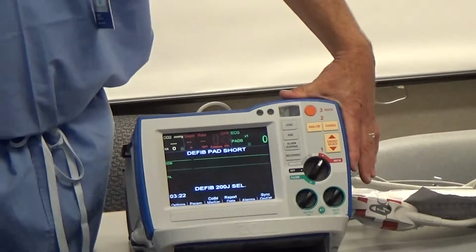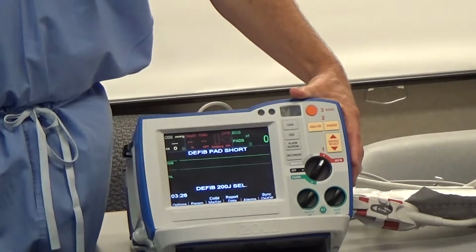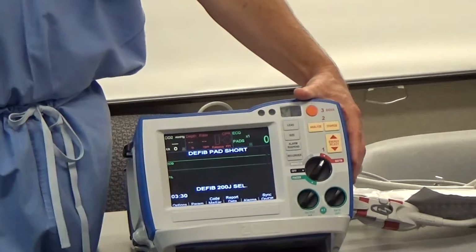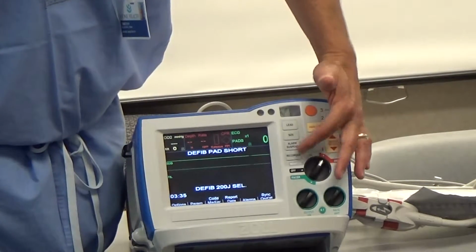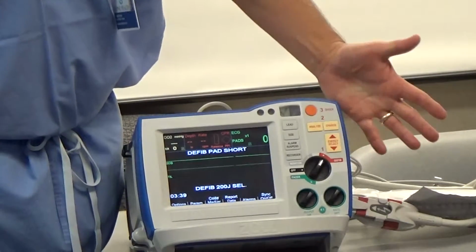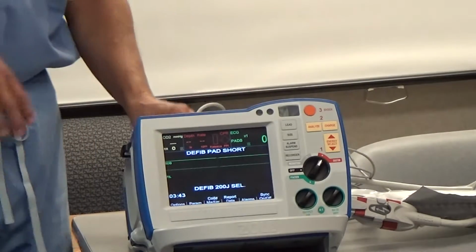Well, let me do a couple of things here. Here's your lead. It's always a good thing to change your lead if you want to. If you're not getting what you want to see, you can push that button and change it to another lead, and it'll shift leads around. That is your size buttons. That is your alarm suspend button. Your recorder, it will record. Theoretically.